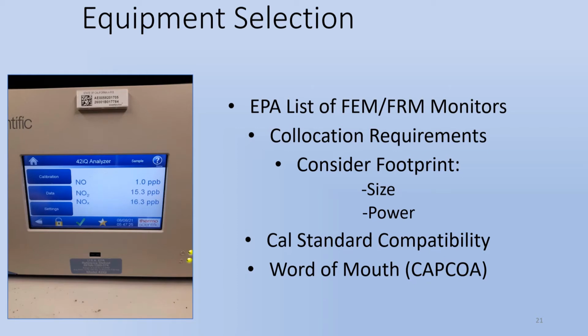Most agencies will already have in-house specifications, but some of the factors you'll want to consider are range. Lower level trace units are becoming commonplace, maybe more so as audit levels drop, so MDLs and response times are important. On the back end, you'll want to specify the signal output so that you maintain network compatibility.